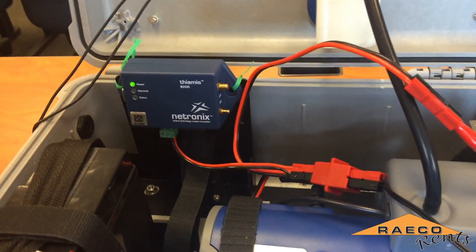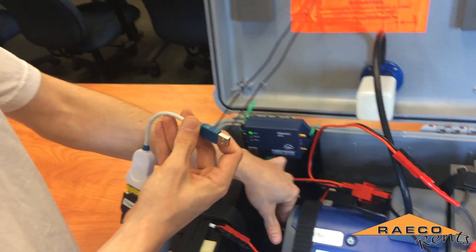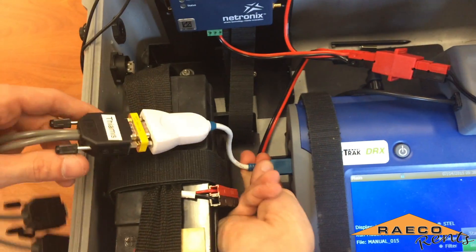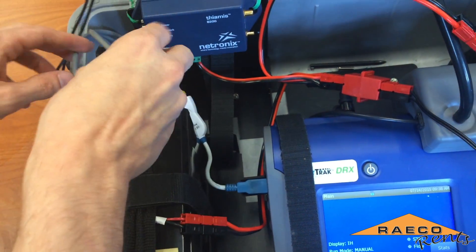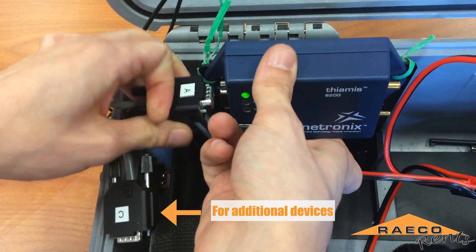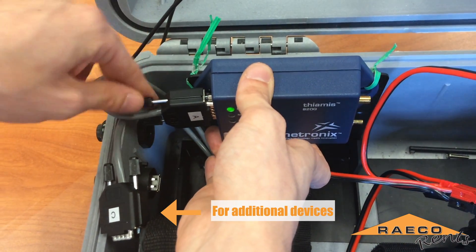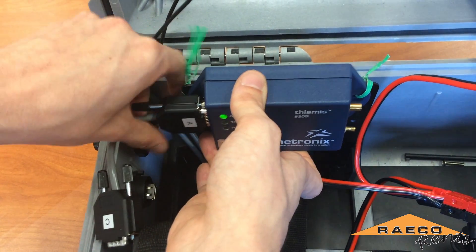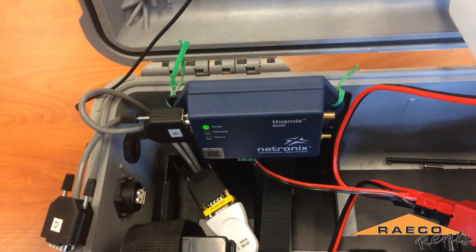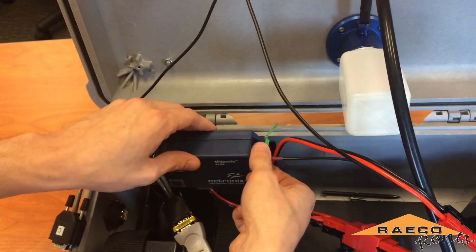The last cable we're going to connect is a serial to USB cable. That's going to transfer the data from the DustTrak to the Thiamis for it to get uploaded to the server — that just screws in there. Then you want to make sure you have your antenna connected so that it can get GPS reception.